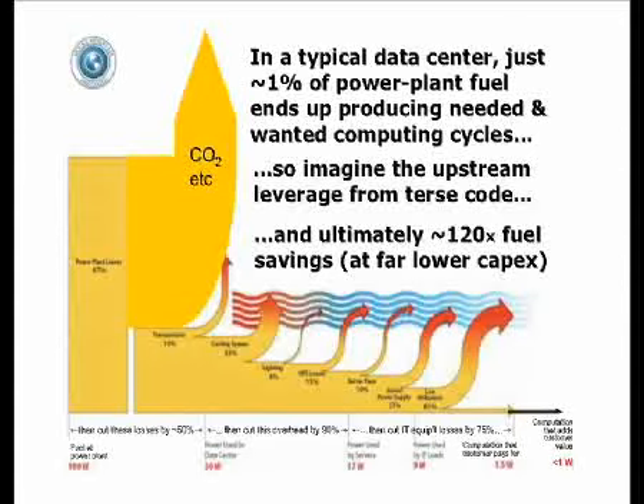Now let's apply this same diagram of reasoning from downstream to upstream to a data center. Normally the operator will just look at the electricity coming in at this point. But actually we have to remember there's grid loss and power plant loss upstream of that. And mostly we only look at the power used by the IT loads. But because of low utilization, only a small part of that actually is working. And it's not just low utilization, it's that we often use servers designed in such a strange way that at, let's say, 1/4 of their computing load, they'll still use 2/3 of their energy. They don't turn down properly. They don't turn off the bits that you're not using, or they don't clock down properly.